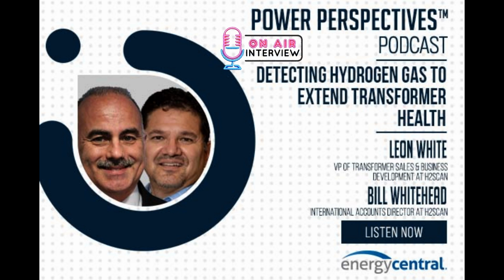Moving forward, maybe into the 2000s, multi-gas sensors were developed and created. These were needed for critical transformers at the time, but there was a big marketing push to put multi-gas sensors on pretty much all large transformers. Even though it sounds like a great idea, these monitors required heavy maintenance and never really lasted that long. Transformers' life expectancy is about 40 years, but these multi-gas monitors only lasted about 10, with pretty heavy maintenance after 5 years. So a big lesson was learned over time.